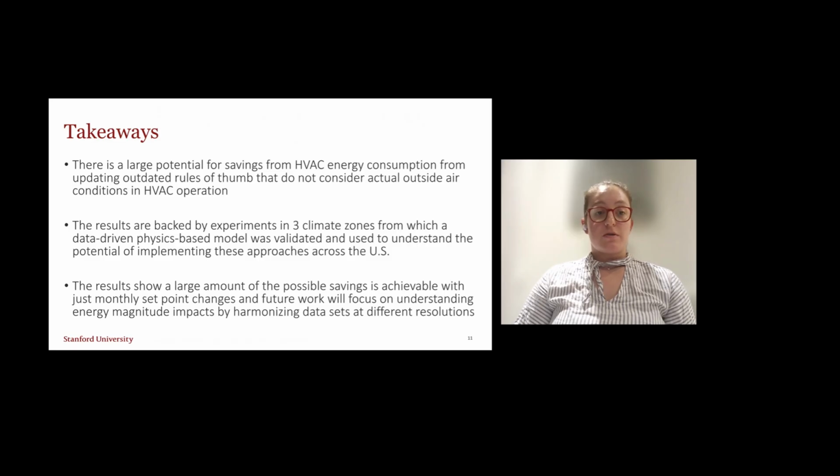I'll leave you with these 3 main takeaways. First, there's a large potential for savings from HVAC energy consumption from updating those outdated rules of thumb that do not consider the actual outside air conditions in HVAC operations. Second, these results are backed by experiments in 3 climate zones from which a data-driven, physics-based model was validated and used to understand the potential of implementing these approaches across the United States.